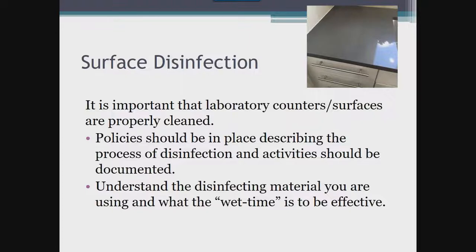All equipment and working surfaces must be regularly cleaned and decontaminated after contact with blood or other potentially infectious materials. Work surfaces should be decontaminated after the completion of procedures and at the end of each shift. The process for decontamination must be followed carefully — there is a defined wet time for various products, and it is critical that these wet times be followed to ensure that the surface is in fact decontaminated. Documentation of this task must be completed within the quality control program.